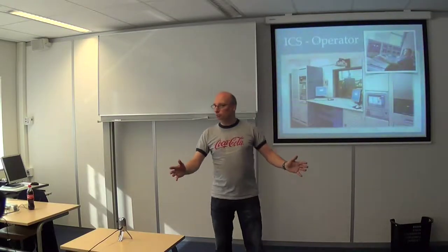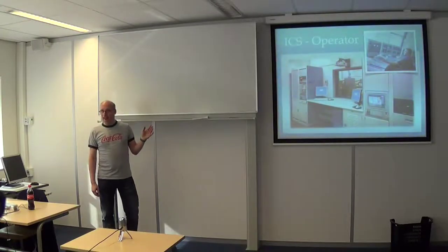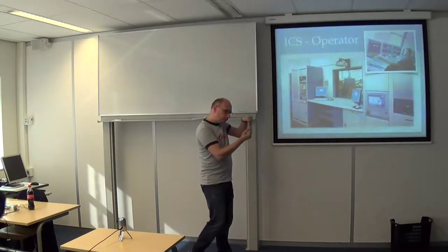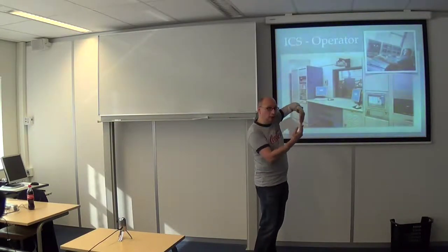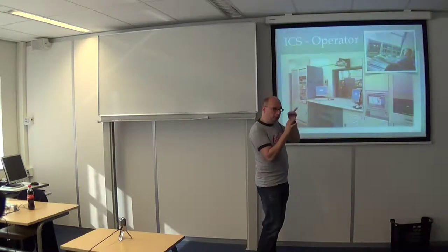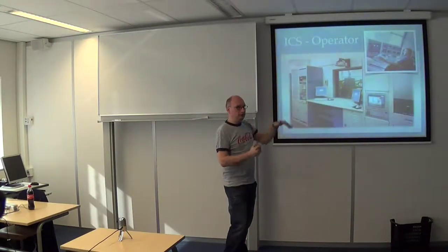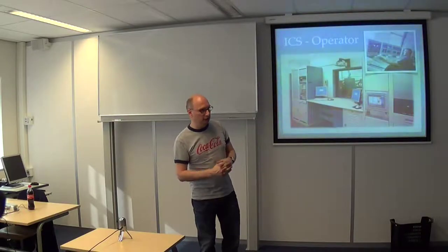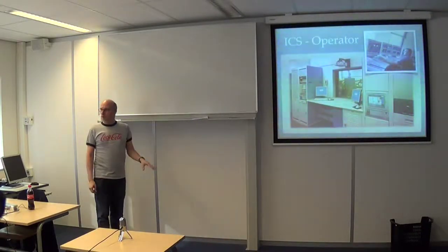The machine is running, and the way these PLCs work is they're redundant. So there's one side of the PLC that's working, and one side which is dormant. And you can mess with that side, you can change the software, and then with a flick of a switch, you switch to the other side, and you have a new active system running. So that's how the updates work. So that's how you can update all the software without interfering with the production.